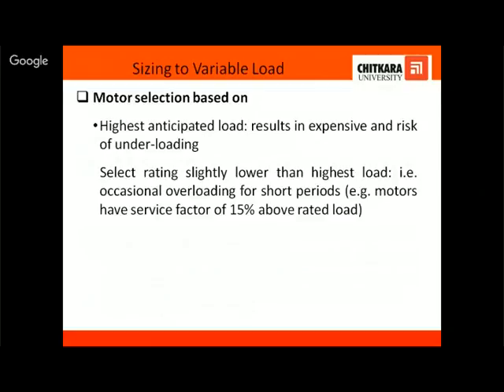Now coming to the second point, that is sizing to the variable load. Motor selection is based on the highest anticipated load, which results in expense and the risk of underloading. Say there is a complete industrial process. During the process, the motor may be overloaded just for a moment, for a very small duration. Instead of taking a motor of that higher size, take a motor for the base load, since motors are provided with a service factor, and 15% or above can be taken. The service factor provides the overload facility for that motor. So during the process, for that momentary period, the motor can be overloaded, but for most of the process the motor will operate at full load and the efficiency will be high. So that is sizing to the variable load.